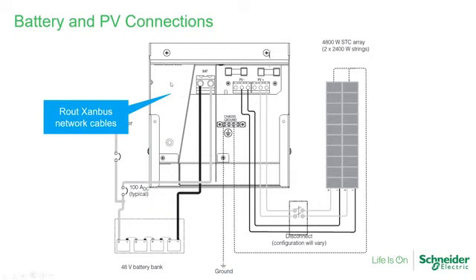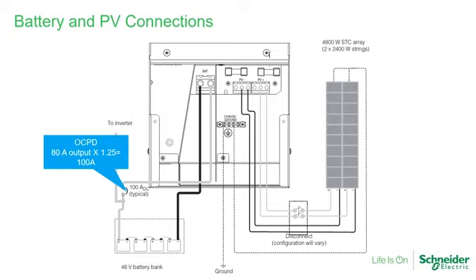Okay, let me jump to the Xanbus so I can stay in order, but I wanted to talk about the overcurrent protection device next. I mentioned that already on the previous slide. This section is not really clear in the photo, but it is a separate tray intended to run communication cables. And this bottom piece is actually another piece of the tray where you can run the communication cables and not be running them with the current carrying conductor.